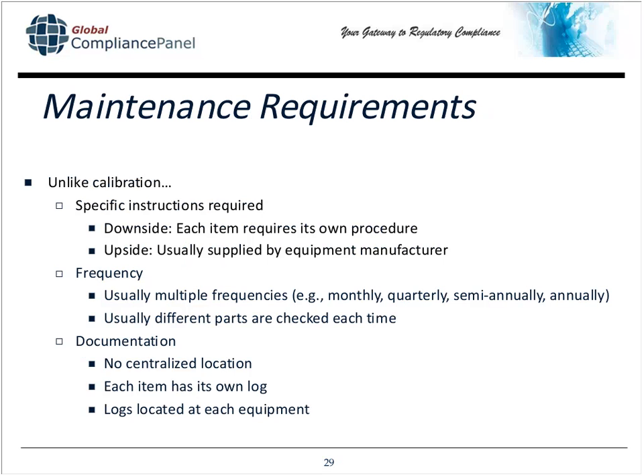So when it comes to maintenance requirements, there are distinctions between maintenance and calibration. Much of this is due to the fact that there are really no international standards for preventive maintenance. This is the downside of maintenance. The good side of maintenance is that maintenance requirements are usually supplied by the equipment manufacturer. When you purchase a several-dozen-thousand-dollar piece of equipment, it comes with an operator's manual that usually has the recommended maintenance, including its frequency. So you can merely take that and fold that into your PM program, which is easy enough.